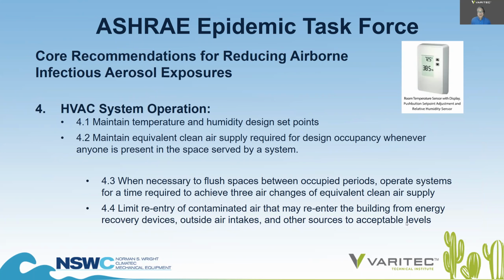HVAC system operation. Maintain temperature and humidity design set points in the space. Maintain equivalent clean air supply required for design occupancy whenever anyone is present in the space. It also offers guidelines on when it is necessary to flush spaces between occupied periods. Operate systems for a time required to achieve 3 air changes of equivalent clean air supply. Limit re-entry of contaminated air that may re-enter the building from energy recovery devices, outside air intakes, and other sources.